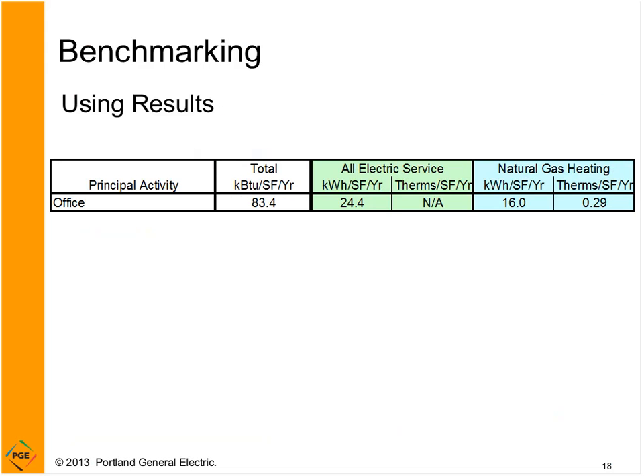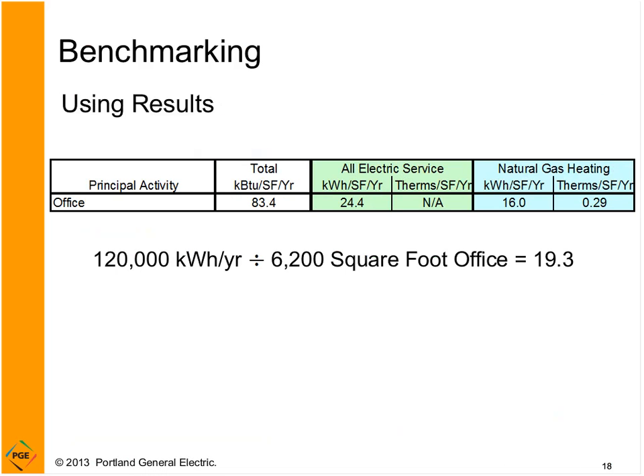So how can we use this information? Let's say we're an office building, and I know by doing my quick graph check that I'm consuming about 120,000 kilowatt hours per year, and I know I'm just over 6,000 square feet. So I do some quick math, and I come up with 19.3 kilowatt hours per square foot per year.